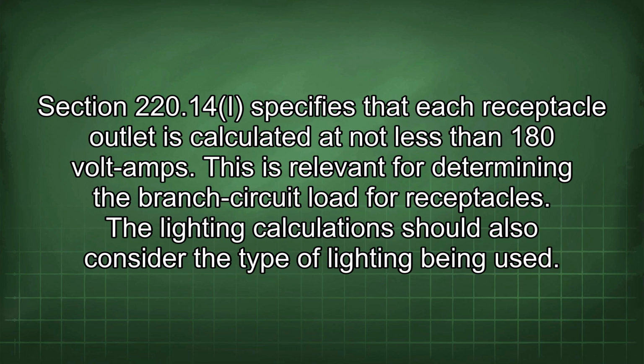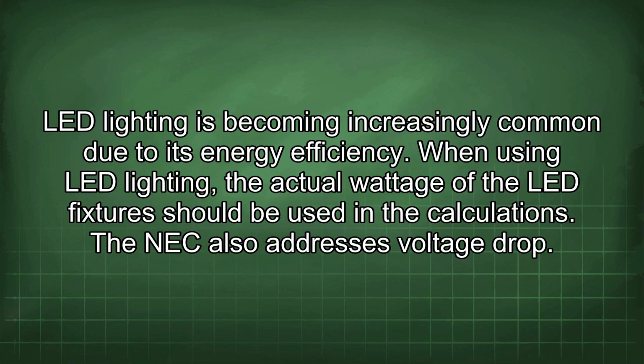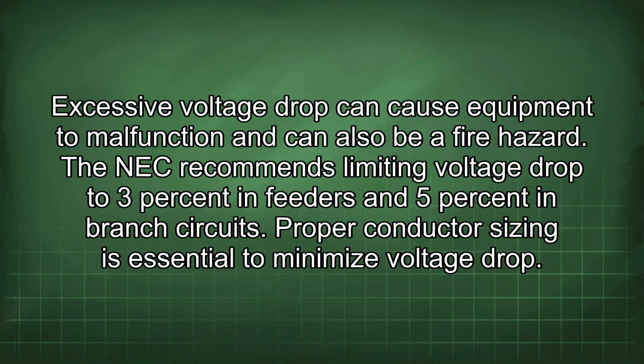The lighting calculation should also consider the type of lighting being used. LED lighting is becoming increasingly common due to its energy efficiency. When using LED lighting, the actual wattage of the LED fixture should be used in the calculations. The NEC also addresses voltage drop. Excessive voltage drop can cause equipment to malfunction and can also be a fire hazard. The NEC recommends limiting voltage drop to 3% in feeders and 5% in branch circuits. Proper conductor sizing is essential to minimize voltage drop.